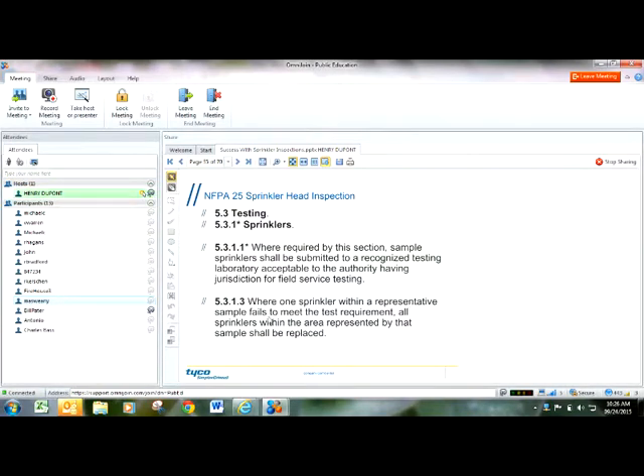Where one sprinkler head fails within a sample, then all of the sprinkler heads fail. So what that means is, say you've got a facility with 150 sprinkler heads total, and they're all quick response sprinkler heads, and they're all 25 years old. A representative sample would be about 4 sprinkler heads. That's out of NFPA 25. I take those 4 sprinkler heads from different locations throughout the entire building, and I send them off to UL.